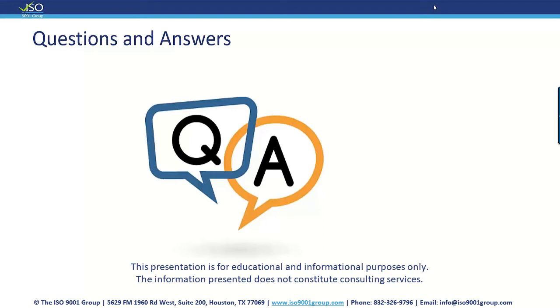Now, they should write you up if your devices are not reading properly and you hadn't sent them out for calibration, or they're not reading properly and you didn't implement a verification program. That would be a valid write-up. But if you implement a verification program, document that your readings are within tolerance, there was no need to send it out for calibration, and it's labeled, they should not write you up for that.